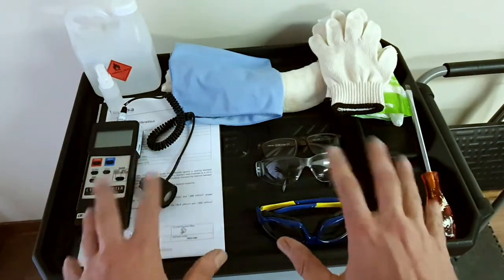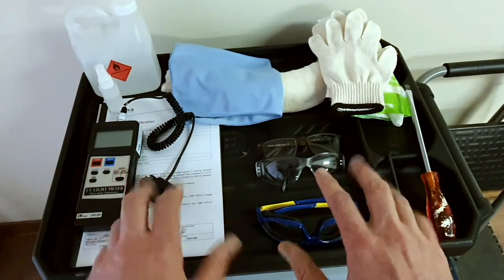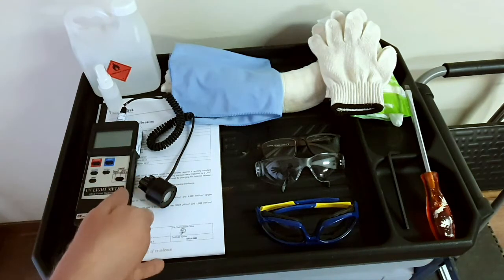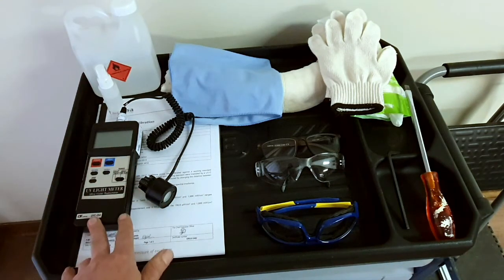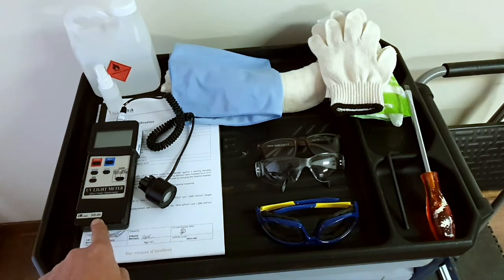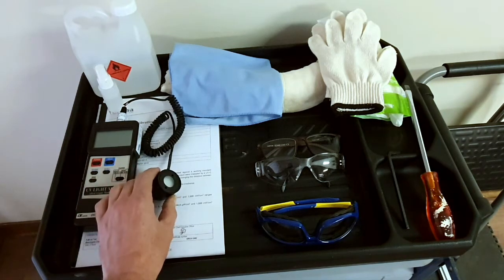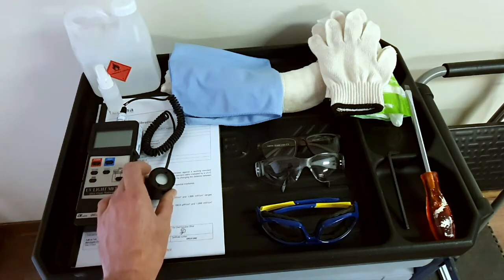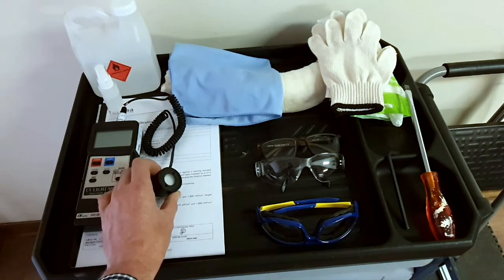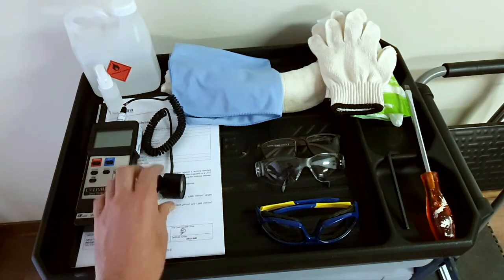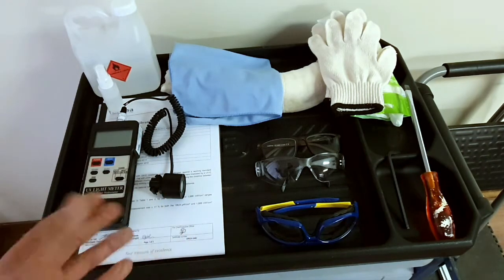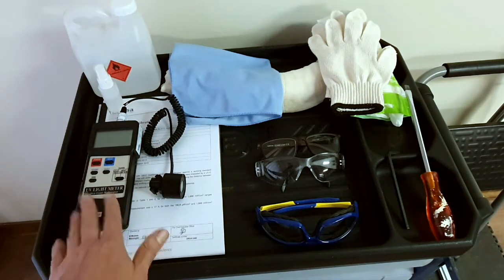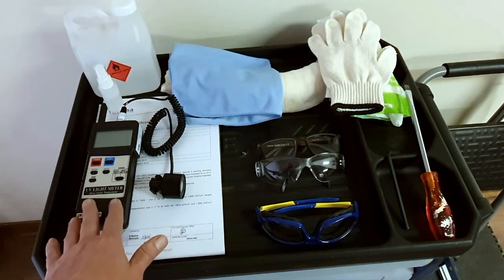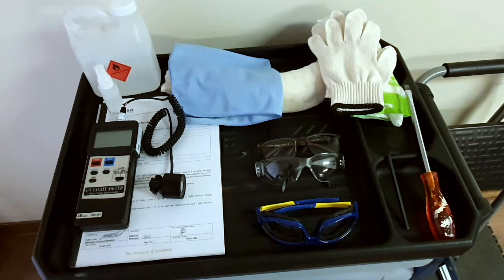I'd like to run through some of the equipment that we'll need to be doing our maintenance. Firstly, the most important thing is your radiometer. This is my preferred weapon of choice. It's a fairly cost-effective UVC radiometer. You'll see it says UVC 254 on there, which means that it has a UVC filter, cosine correction filter on the sensor, which is exactly what we need. Probably not the best radiometer in the market, but good enough for our purposes.